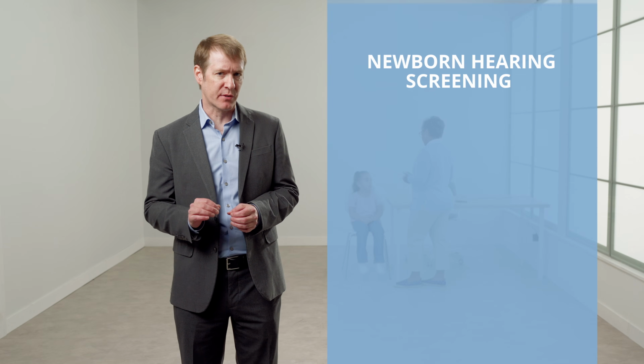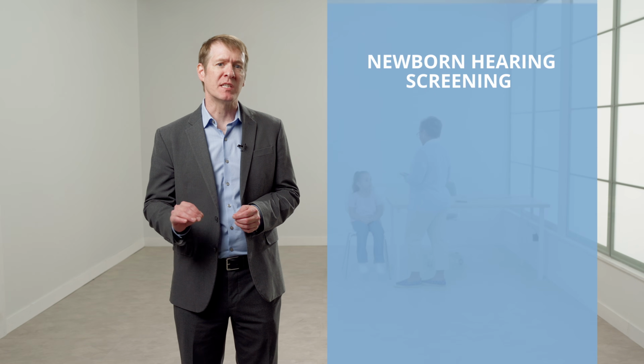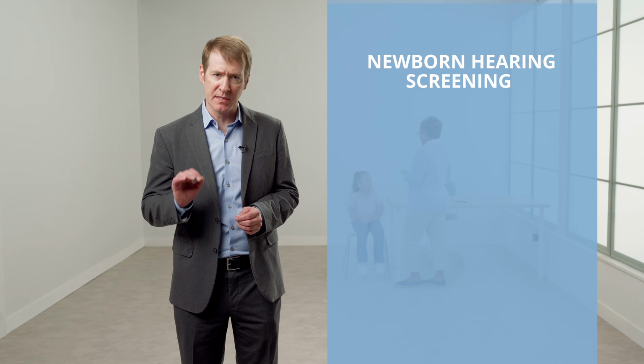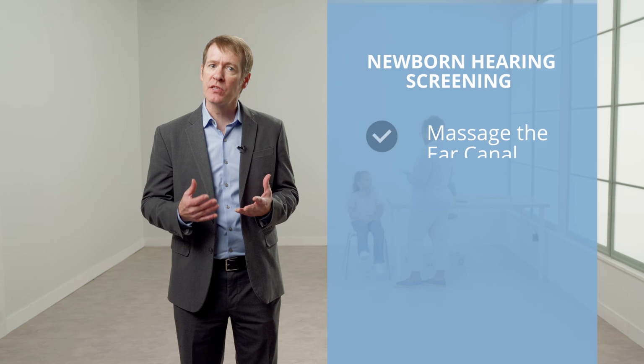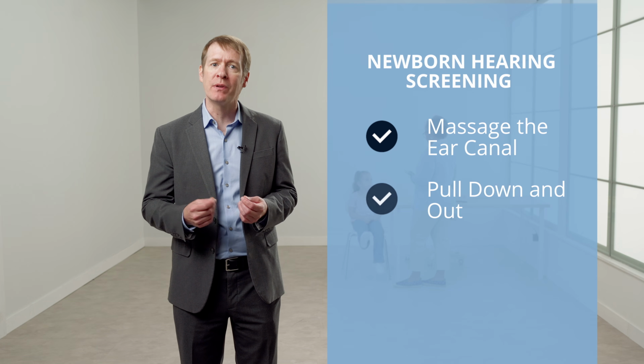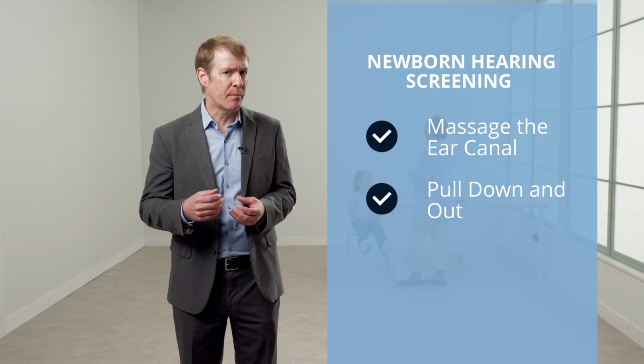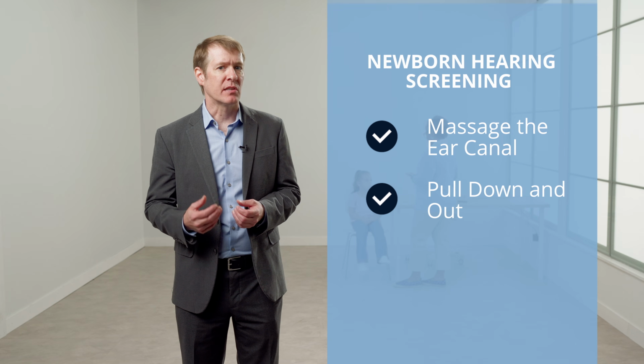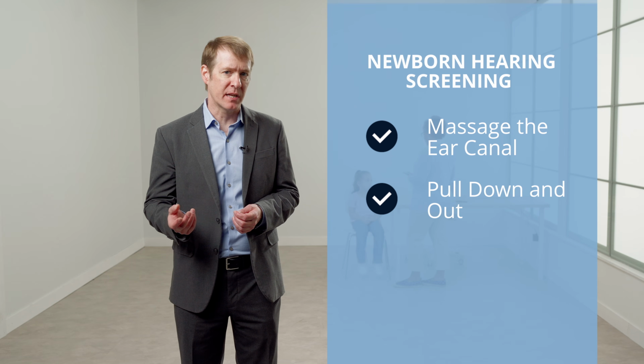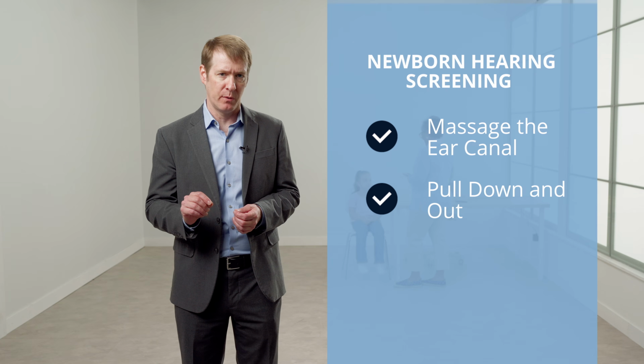It is important to test in a quiet room such as a small office or patient hospital room with the door closed. For newborn hearing screening, the OAE probe must be securely inserted into the baby's ear canal. Massage the front of the ear canal and pull down and out on the outer ear to pop open the ear canal. Select the appropriately sized ear tip and place it firmly on the probe.